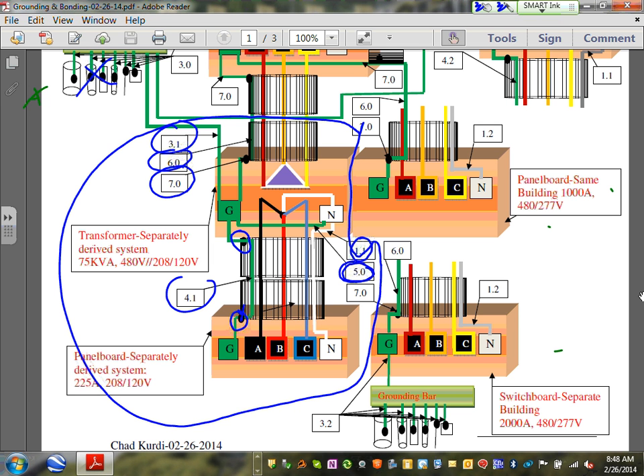Any questions about bonding and grounding of the separately derived system? Can you guys see any connection between the ground and the neutral inside the panel here? No. They only bond them once, either in the transformer or in the panel, typically inside the transformer. So you are not allowed to bond the ground and the neutral again inside the panel. So separately derived system, you bond the neutral once. Can I bond it inside the panel? Yes, but you have to get rid of this little wire here. You have to remove that wire.